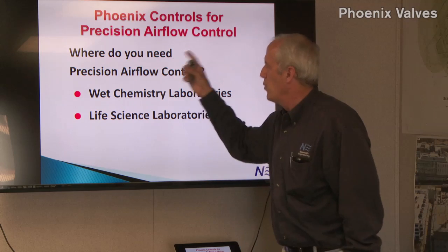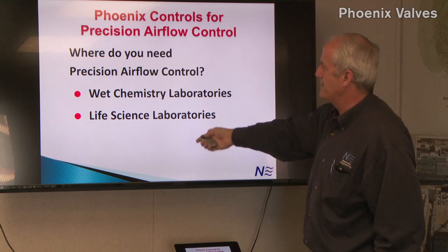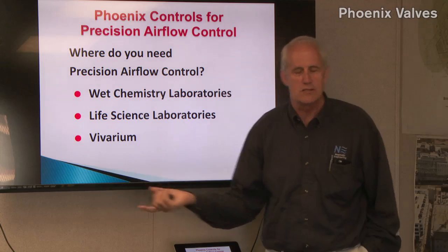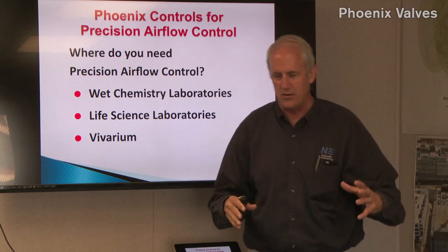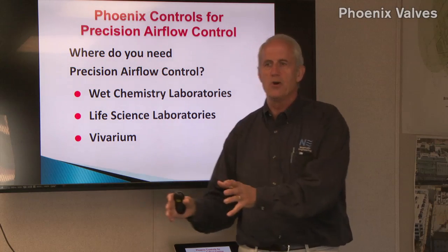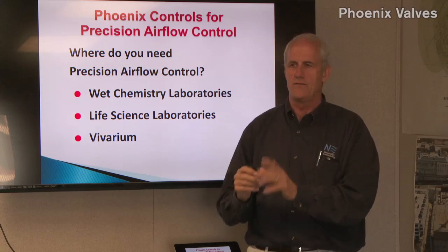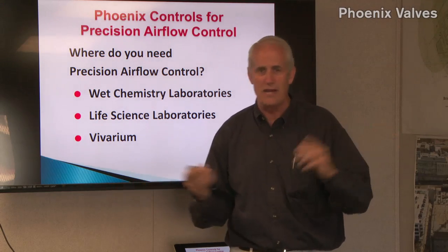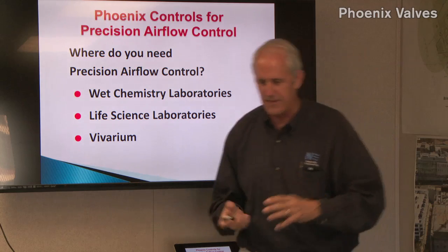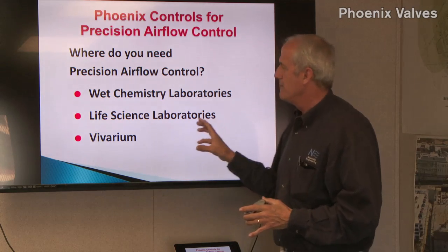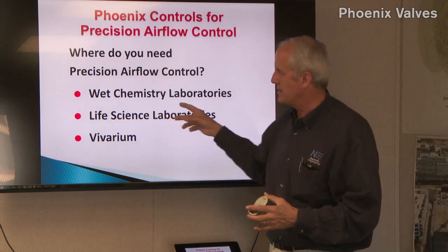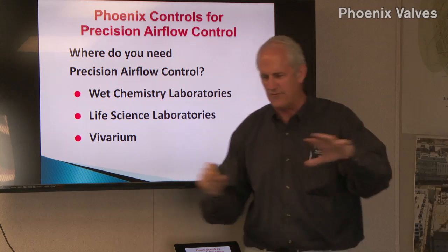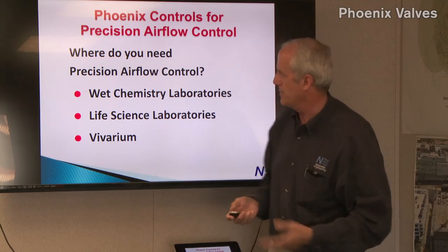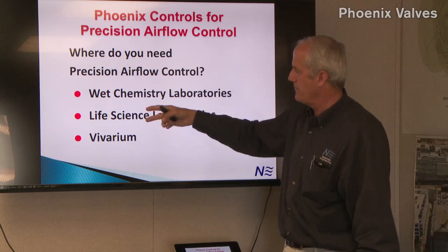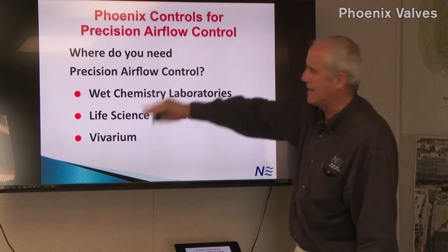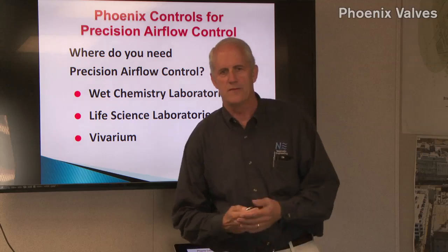Now, where do we do it? Phoenix does wet chemistry labs, life science labs, and vivariums. Again, here is mostly vivarium. Other than the vivarium, you have some fume hoods, but the fume hoods are all constant volume fume hoods. But if it goes into alarm, you're going to have to know how to work on it. We'll talk about that as well. So the main place where we have them in the life science area of the building is on fume hoods. We also have some point exhausts and other things in there. But again, mostly the vivarium, fume hoods, and some point exhausts. There is no wet chemistry in the Alton facility.